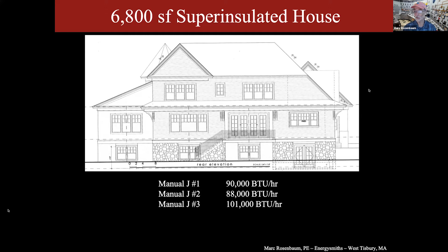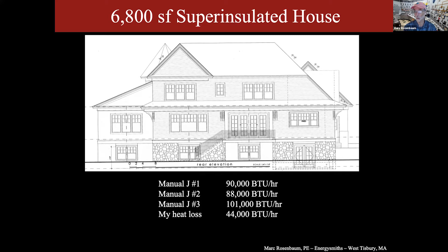That's my heat loss. This building's built. It's designed to that heat loss, and it's been lived in through some fairly severe weather, and it's got plenty of capacity. So what's happened in this first case? The biggest error is overestimating infiltration, really overestimating infiltration. And the consequence would be a vastly oversized system that would work really badly compared to a right-sized system.